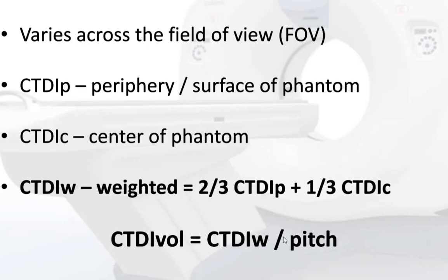CTDI-W, or weighted, varies across the field of view. It factors the dose at the periphery of the body and the dose at the center. The dose at the periphery or skin will be larger than at the center, but CTDI is measured by phantoms. CTDI-W equals two-thirds of CTDI periphery plus one-third CTDI of the center.